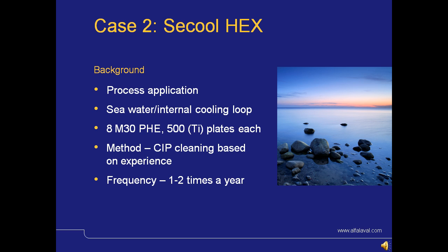For this matter, in order for the plates not to corrode, the heat exchanger plates are most often done in titanium. In this case, the customer has 8 M30 PHEs, again a big size of heat exchangers, with 500 titanium plates each. The customer used CIP, cleaning in place, the chemical cleaning. The frequency was once or twice a year and was based on experience. In the summer, the cooling needs are often the biggest, so the customer cleaned in the spring.